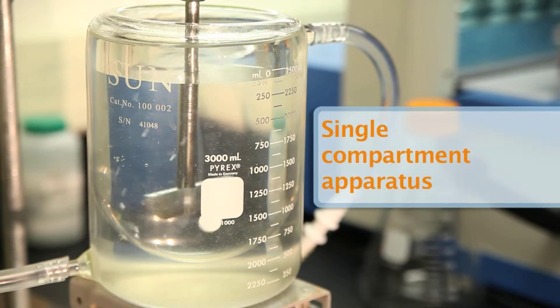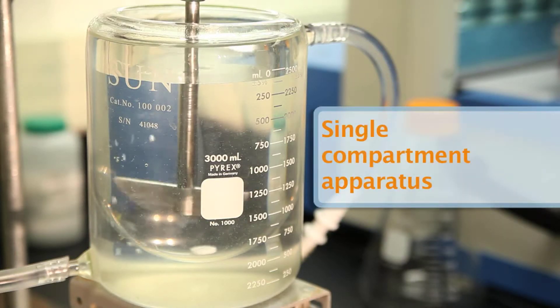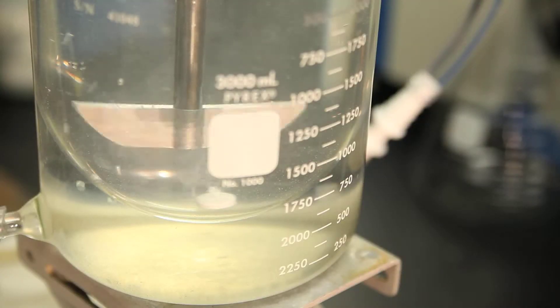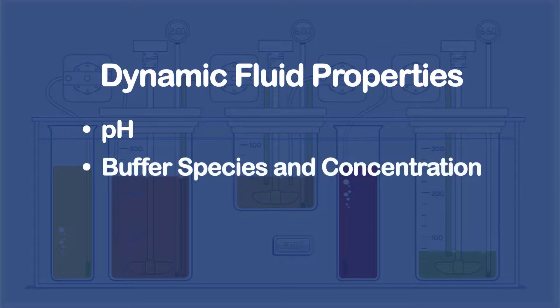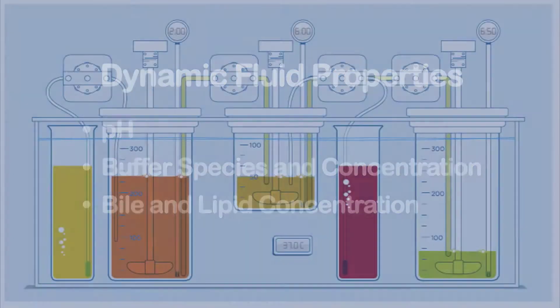The GIS provides a better representation of the physiological environment than conventional single compartment dissolution devices. These typically contain an unrealistically large volume of a single type of fluid. The fluid properties in each chamber within the GIS, such as pH, buffer species and concentration, as well as bile and lipid concentrations, can be designed to mimic the desired gastrointestinal segment.